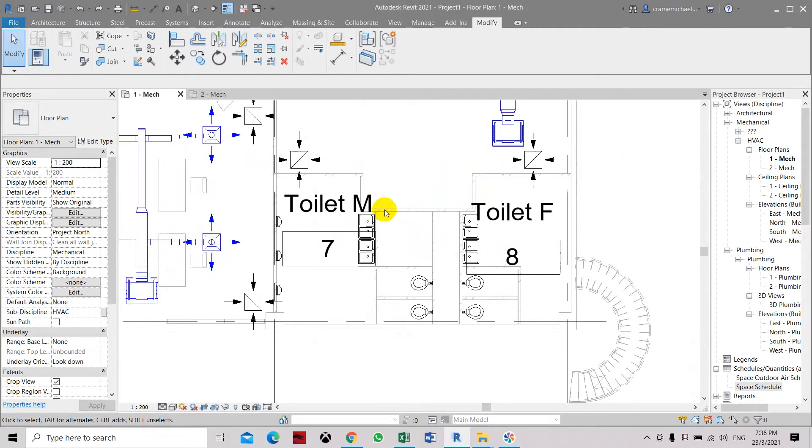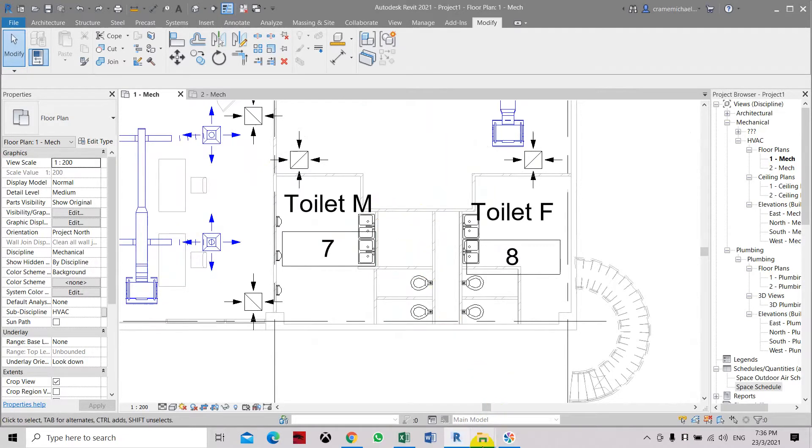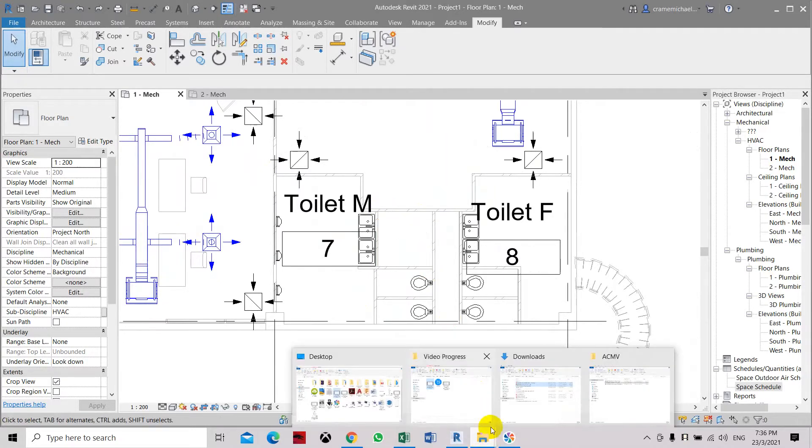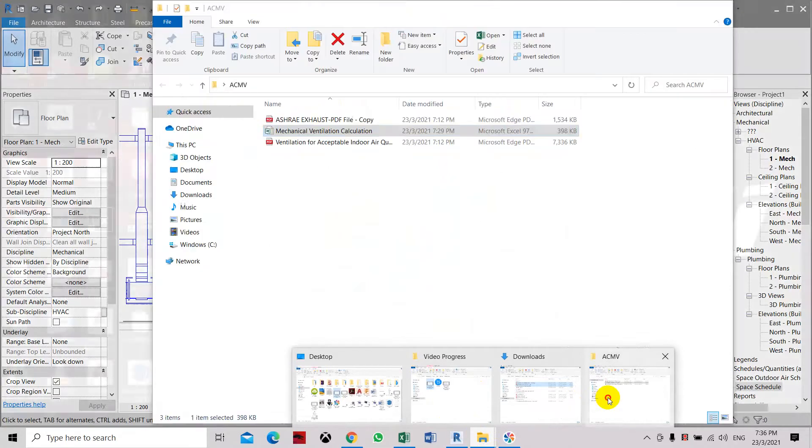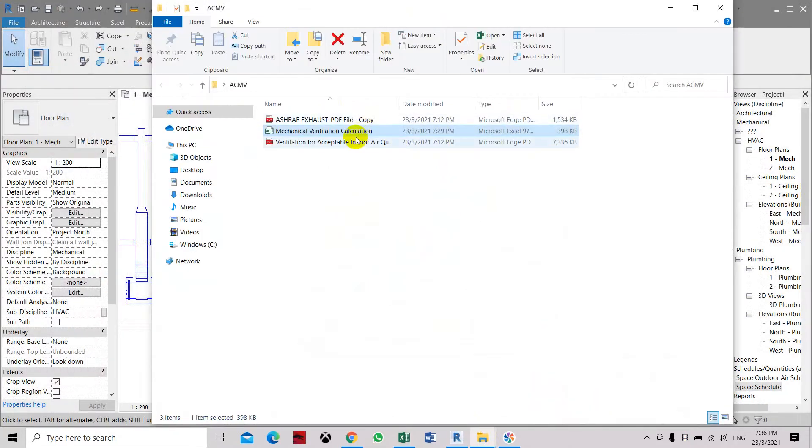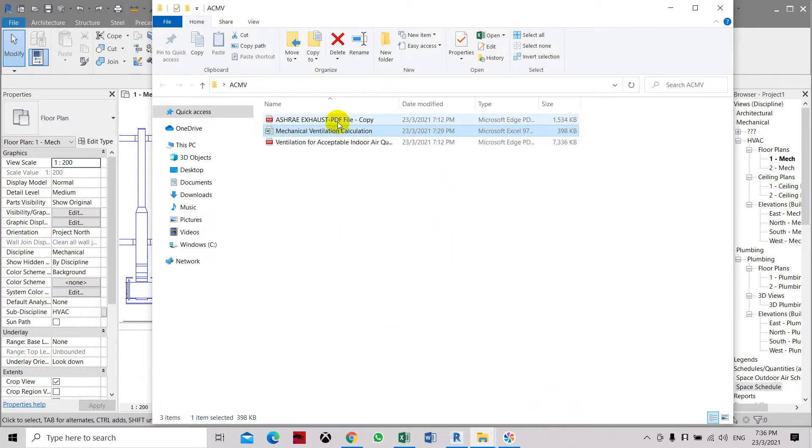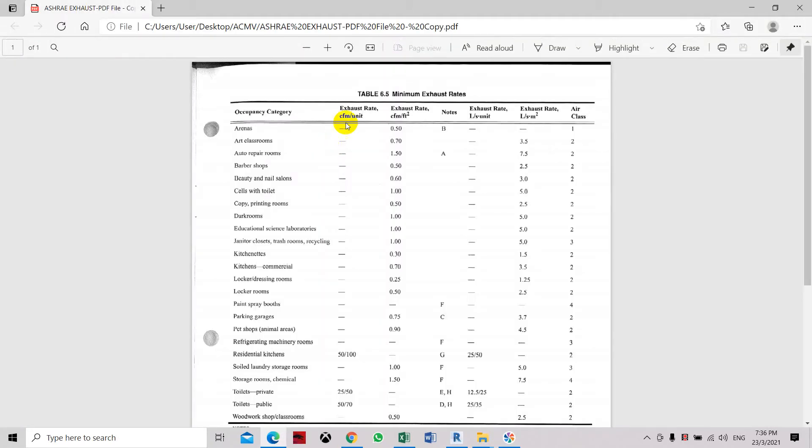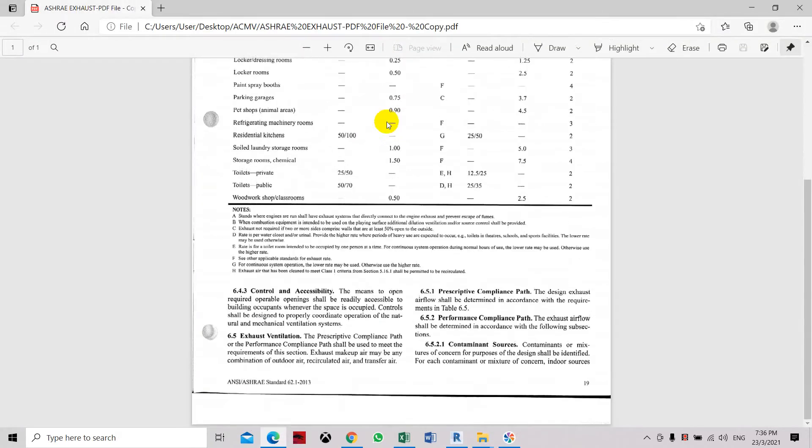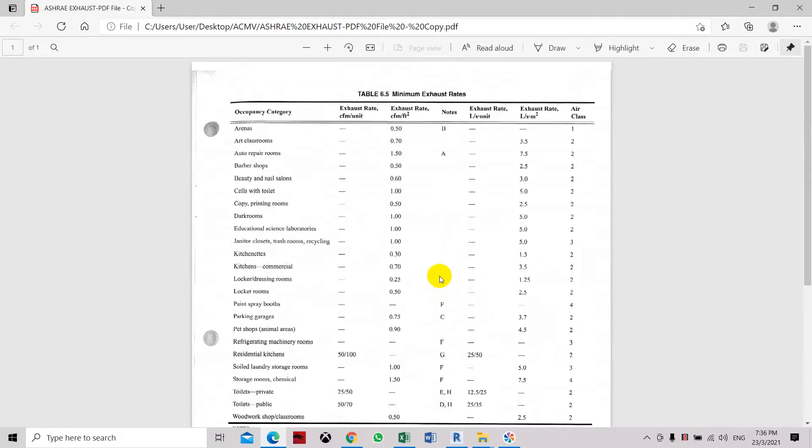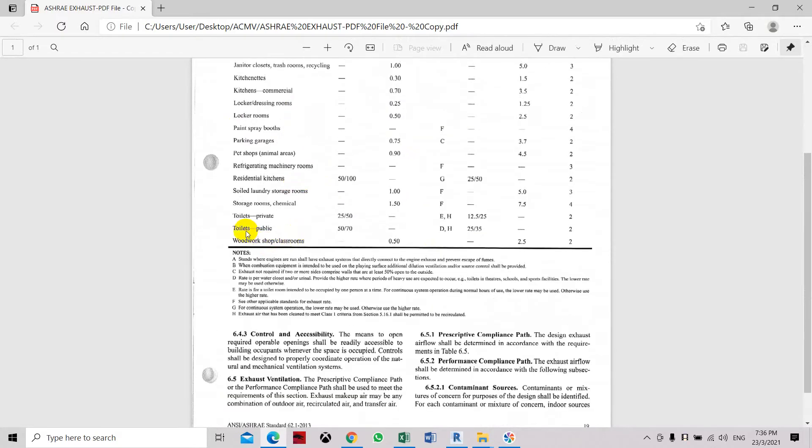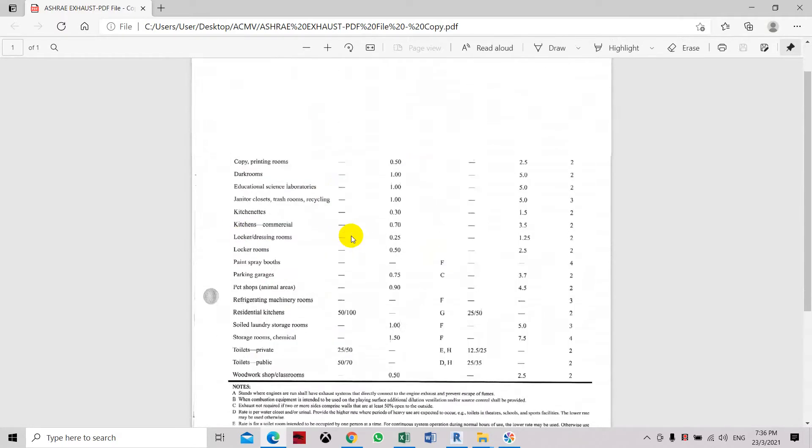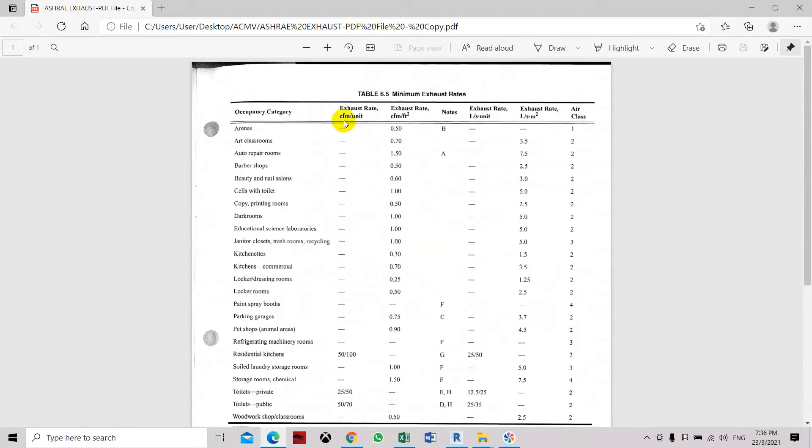First is following the ASHRAE standards which I have here. Here there is exhaust ventilation requirements. Here under the ASHRAE standard 62.1, the minimum exhaust rate for occupancy category of toilet public is about 50 to 70 CFM per unit.